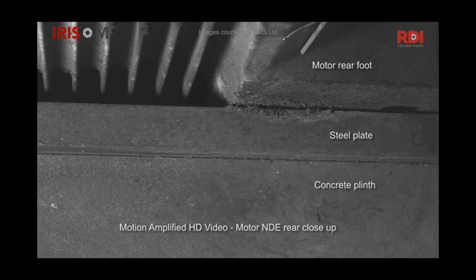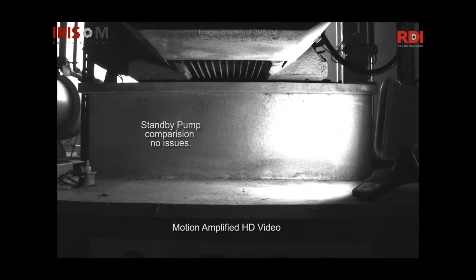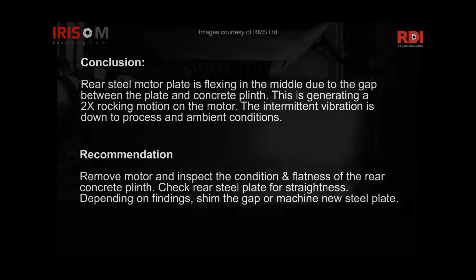So again, having the camera with a route and going straight to the camera to diagnose, because a high 1 times vibration could be 20 different things. Looseness, maybe balance, soft foot - those are more typical, but not guaranteed. And so now we can come up with a recommendation.